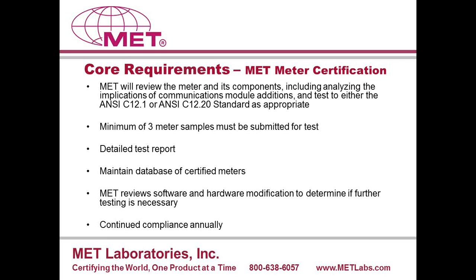Now again, we talked about the series test. If we were going through a test program, we would have to have 3 samples going through the series test. The identical serial numbers would have to go through those 8 tests that I mentioned earlier. But we could have additional samples available to run tests concurrently, in parallel, for some of the other applicable tests. And we would have the flexibility to expedite a test program and get everything through, testing the minimum number of 3 samples, but they wouldn't need to be the same serial numbers for the non-series set of tests.